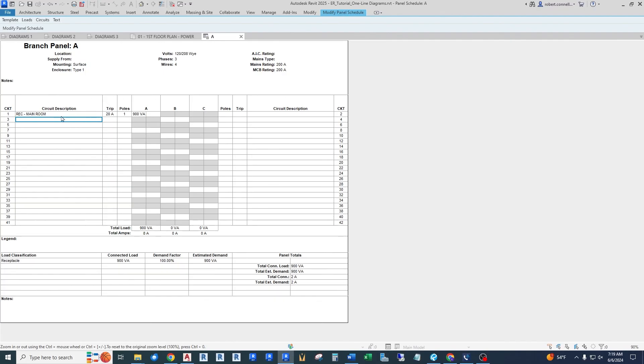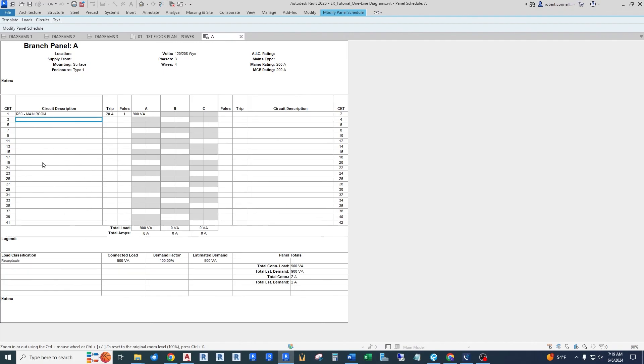And it tells circuit by circuit circuit one, what is that serving? It's serving the receptacles in the main room. That's a 20 amp trip rating, 20 amp setting for that breaker. It's a one pole breaker, and there's 900 volt amps, or pretty much 900 watts on that circuit. It's added up all those receptacles. And this would be shown for each circuit. So this is a third piece of that wiring diagram that we looked at for the panel.